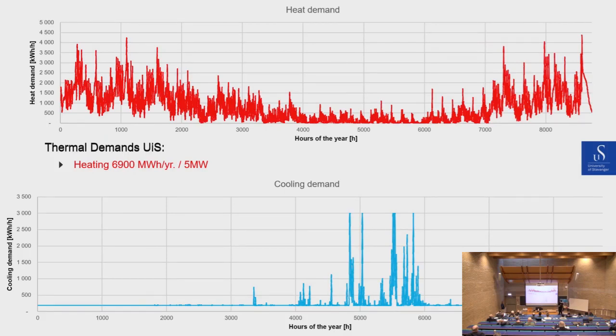And let's put up the cooling demands as well. The maximum cooling demand is 3 megawatts. You see that occurs quite seldom, while the heat demand goes along all the time. But the cooling demand needs to be met. That's an interesting point. A cooling process is basically the removal of heat. So if you're doing these calculations to compare various systems, with a heat pump system like we are talking about today, you get both heating and cooling from the same unit, and that can help the economic calculations.